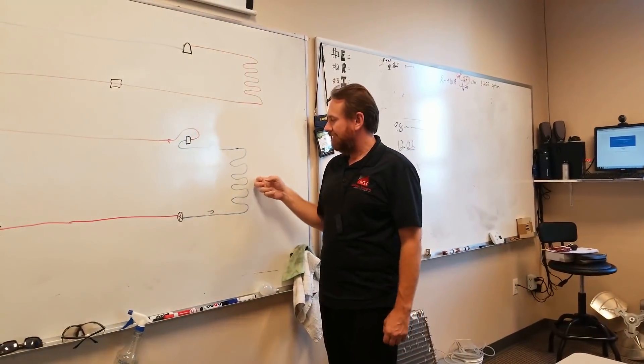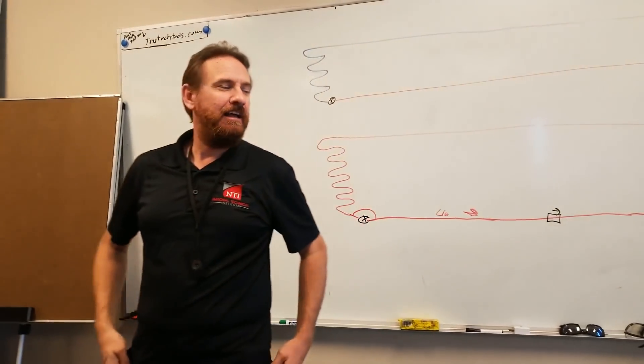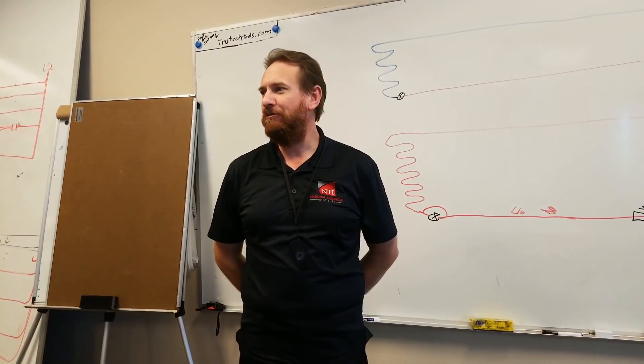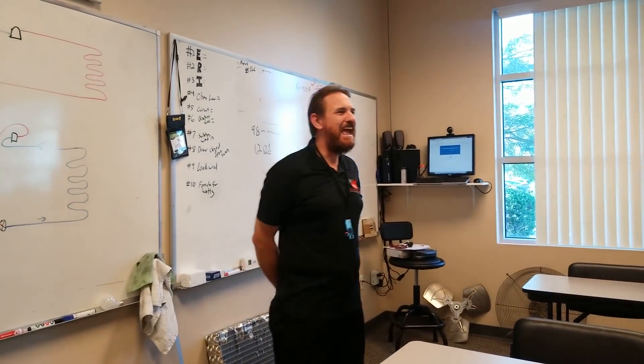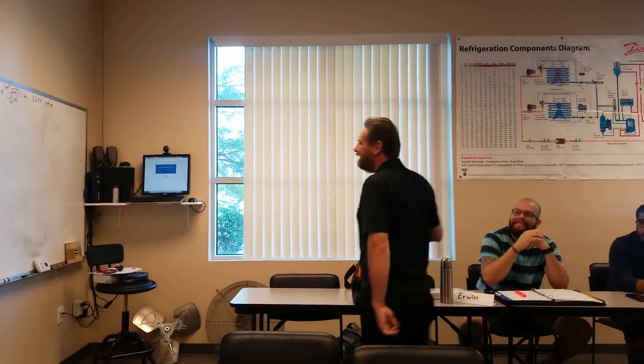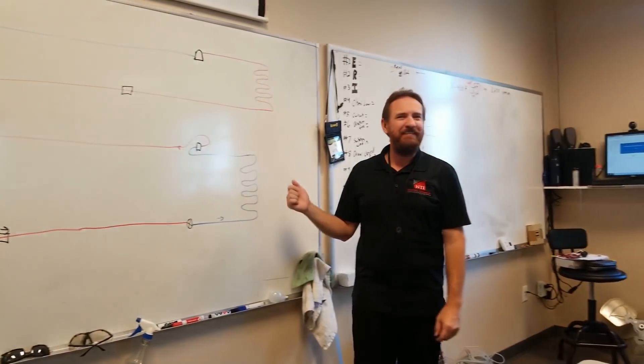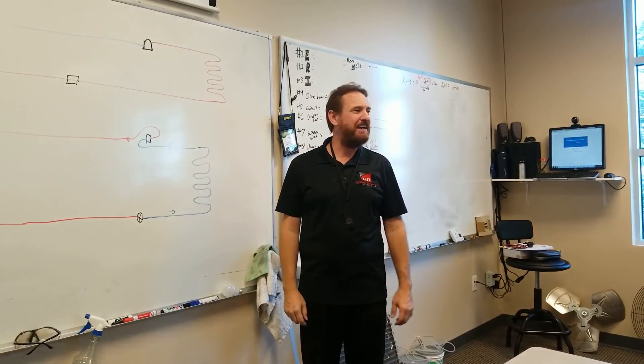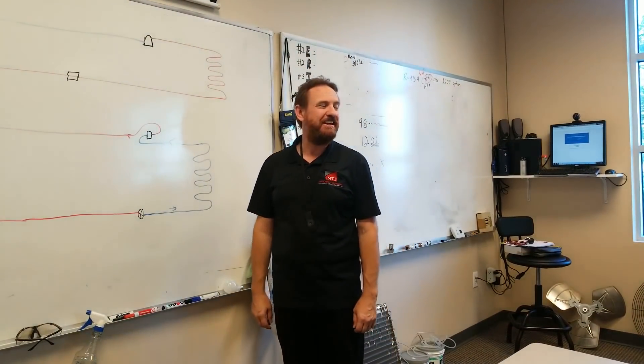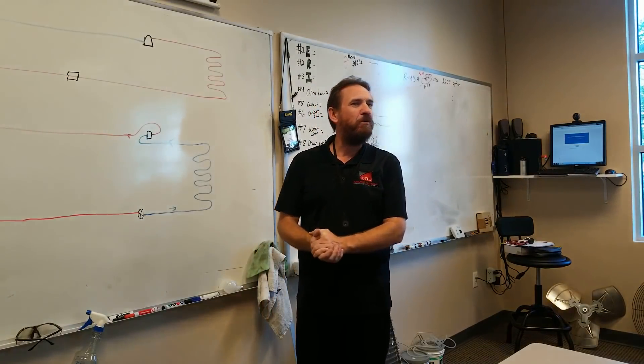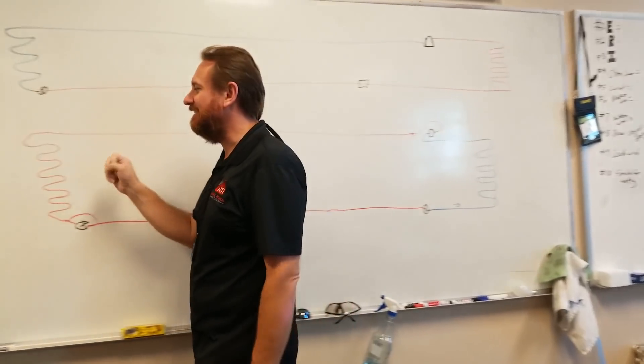A heat pump absorbs heat from outside and rejects heat to the air inside. As long as my saturation temperature is below the air temperature, I can absorb heat. People always say, isn't it cold outside — you can't absorb heat because it's cold outside. But you can, because there is heat all the way down to minus 460 degrees Fahrenheit. There is always heat — there is no cold. Even though the temperature outside drops below zero, there's still heat outside. At zero degrees Fahrenheit, there are still 460 degrees worth of heat. Now it gets more difficult to absorb it, more work, but there is still heat outside.